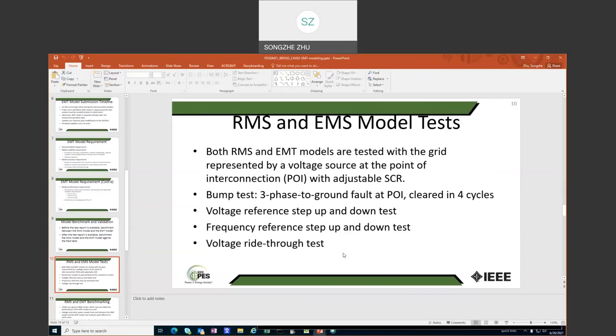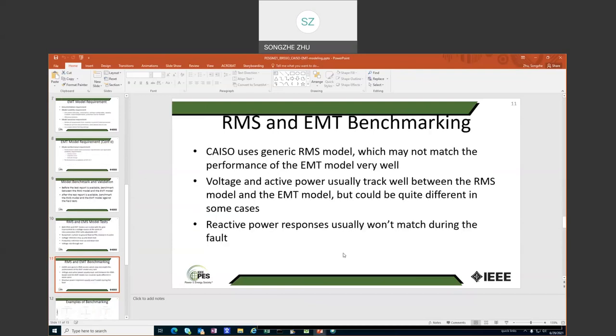And then the voltage ride-through test. The voltage ride-through test is actually a playback of a certain voltage profile at the POI, and then we observe whether the inverters can ride through that or not. The same tests are performed for both the RMS and the EMT model.